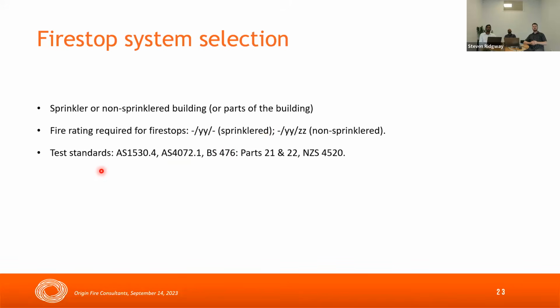The next step is choosing the fire stop system. According to the building code, the fire stop system must be tested to AS 1530.4 and AS 4072.1, and wall construction or ceiling construction must be tested to BS 476 parts 21 and 22. And NZS 4520 is the fire door standard. So we choose fire stop systems that are tested to these standards.